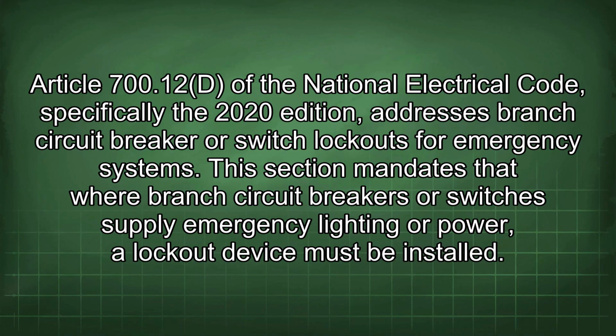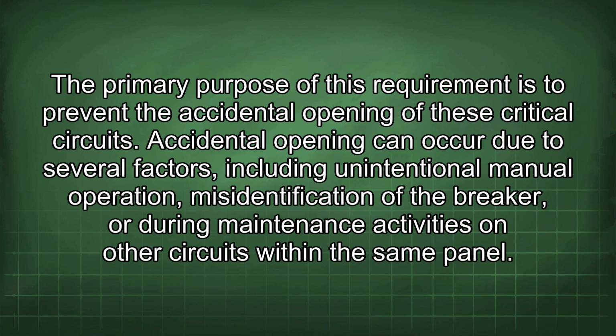Article 700.12(D) of the National Electrical Code, specifically the 2020 edition, addresses branch circuit breaker or switch lockouts for emergency systems. This section mandates that where branch circuit breakers or switches supply emergency lighting or power, a lockout device must be installed. The primary purpose of this requirement is to prevent the accidental opening of these critical circuits. Accidental opening can occur due to several factors, including unintentional manual operation, misidentification of the breaker, or during maintenance activities on other circuits within the same panel.